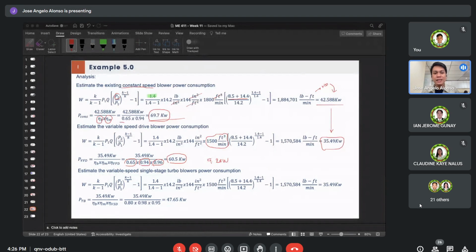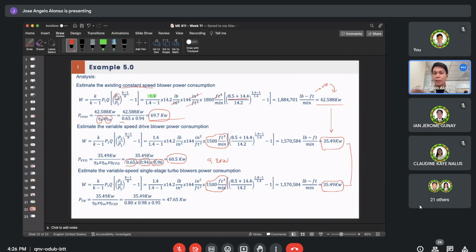Lastly, let's estimate or determine the variable speed single turbo blower power consumption. Since both have VFDs, both will use 1,500 cubic feet per minute, and both will have the power imparted to fluid as 35.49 kilowatts. So it's the same as the VFD case since both have VFD installed. They will only differ in power consumption because the efficiency of the turbo blower differs from the motor, blower, and VFD efficiency of the other. The turbo blower is more cost efficient if we look at it.